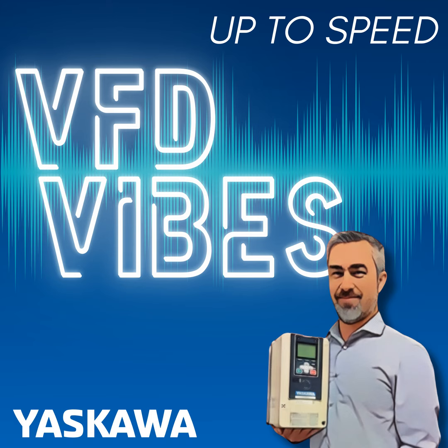In that situation, we're now missing an AC wave coming in, one of the 3 waves, and there's a gap in the charge that's applied to the DC bus. And if we're running that motor at speed, we're pulling a lot of power from that DC bus. With that missing phase, we now have a fluctuation in voltage that goes outside of an acceptable range. And that generates an input phase loss fault. The drive monitors that bus ripple, and if it exceeds a limit to protect the capacitors from failing, we fault out.